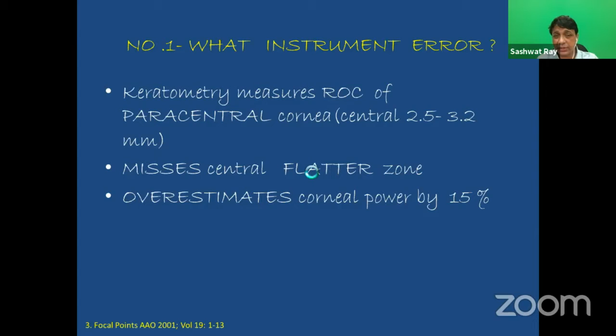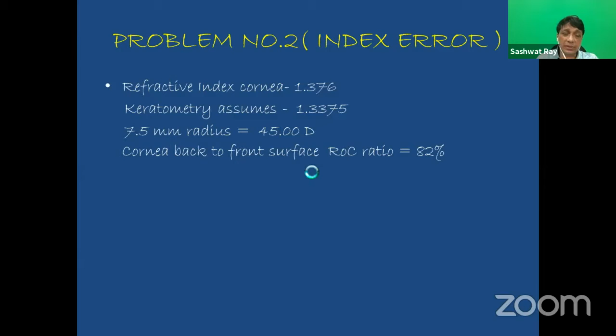The second problem is an index error, which is due to an assumption which was made in the infancy of keratometry. The normal refractive index of the cornea is 1.376, is it not? But the assumption states that it is actually 1.3375. Now, why is this? This is because if we take this assumption, then it converts a 7.5 millimeter radius of curvature of cornea into a nice round figure of 45 diopters keratometry. That is why it was taken. But remember, this assumption is only true for a virginal cornea, when the corneal back to front surface radius of curvature ratio is 82%, which is normal.